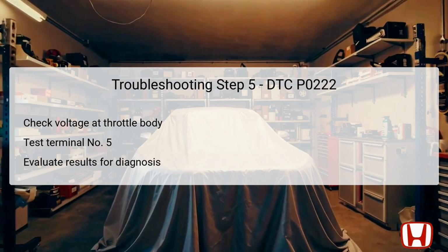It is essential to ensure this terminal's voltage is at expected levels. Discrepancies suggest a failure in the circuit or in the TPS itself. Post-testing, if results fall within expected ranges, further diagnostic steps may be unnecessary. Otherwise, further disassembly and testing may be required to chase the source of low-voltage faults.